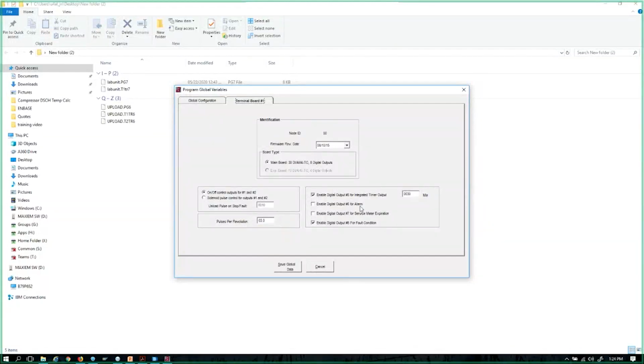I have some global things right here that I can do for the digital outputs. Remember, number 1 terminal board from last week's class, we have 8 digital outputs on it. So I can assign some global assignments here. We'll cover them one at a time. This first option is to enable digital output 5 for integrated timer output. You can see that I have the default set as 30 minutes. So if the unit is running, this output will be turned on. Once it shuts down, it'll remain on until a timer of 30 minutes expires, and then that digital output will turn off. And we can use this for a number of things. I happen to use it in this lab piece to simulate shutting off power to an external device, such as an engine system or an aftermarket air-fuel ratio control system.